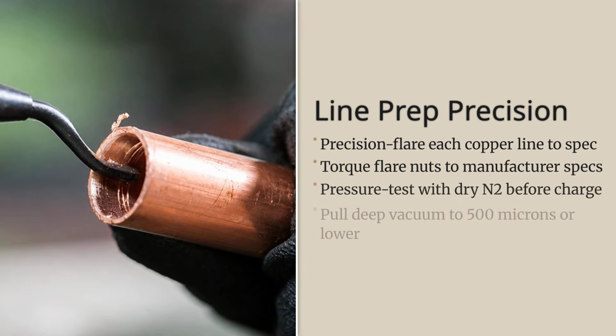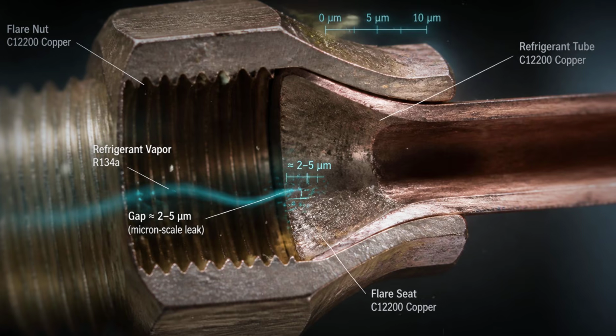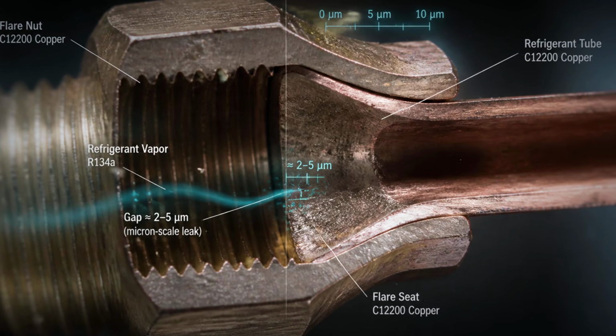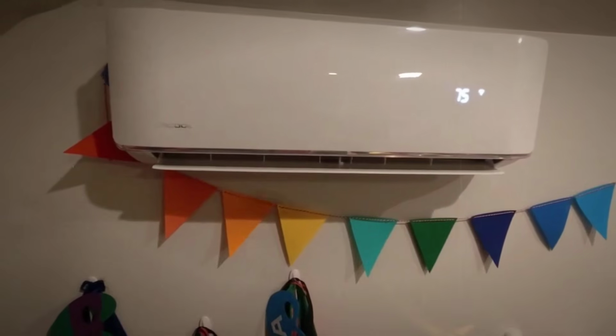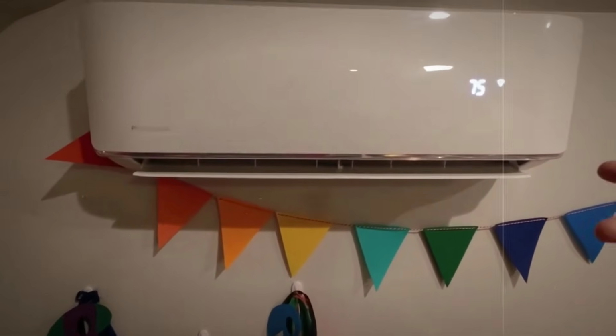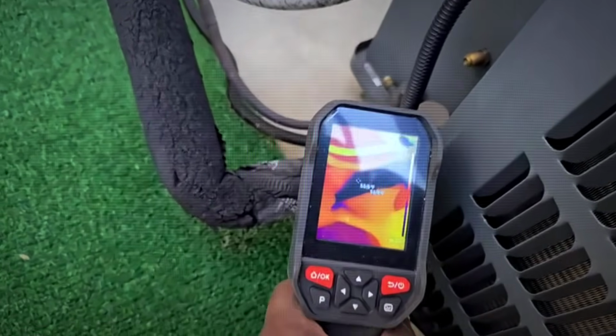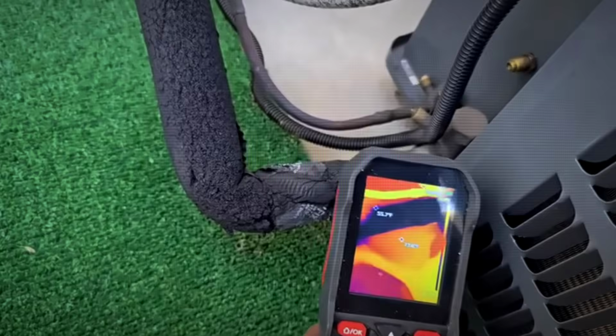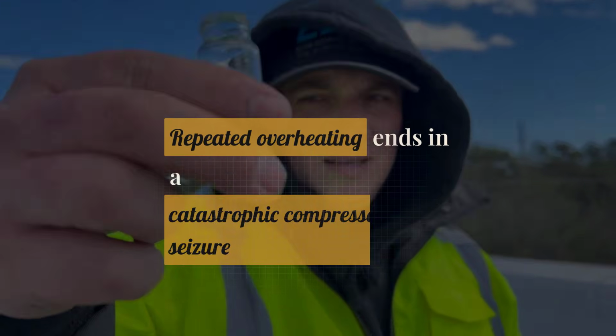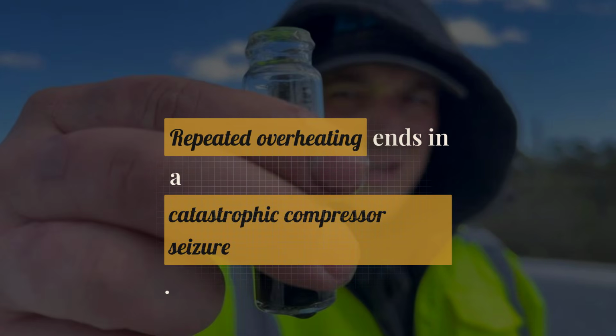A ductless mini-split system operates on copper refrigerant lines that must be precision flared, torqued to exact specifications, pressure tested with dry nitrogen, and then deep vacuum sealed before the system is charged. One microscopic gap at a single flare nut connection, invisible to the naked eye, and the system slowly loses refrigerant charge over the following months. The compressor runs increasingly hot as the charge drops, overheats repeatedly, and eventually suffers a catastrophic seizure.